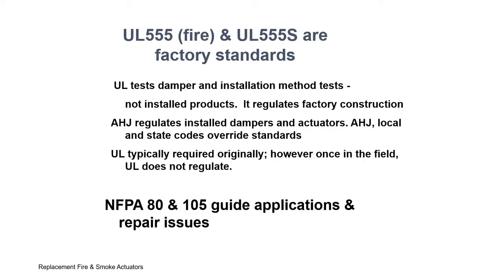Okay, so UL 555 and 555S are factory standards. They test the damper, cycle the actuator and damper. It's tested at elevated temperatures and its leakage. But once installed, it's your AHJ who is in charge of everything. And then, of course, any local standards or codes override the national. There's some cities who require once a year testing. But once in the field, UL doesn't regulate that. NFPA 80 and 105 are referenced by the codes and they take over once installed. And they say, repair the damper as soon as possible. And your actuators are your number one failure point. They're the most complicated part of it.